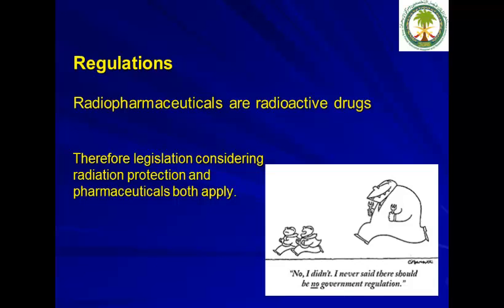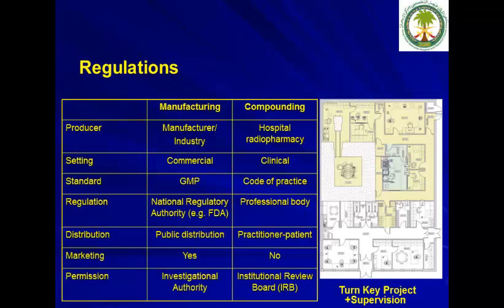You must meet regulatory requirements. Since radiopharmaceuticals are radioactive drugs, both radiation protection and pharmaceutical legislation apply. You need to determine whether you are a manufacturing or compounding facility — a manufacturing facility requires permission from authorities such as the FDA, whereas a compounding facility not selling products may only need IRB approval. It is very important to consult the regulatory body from the very first phases, including during blueprint review, construction, and after completion, to avoid project delays.